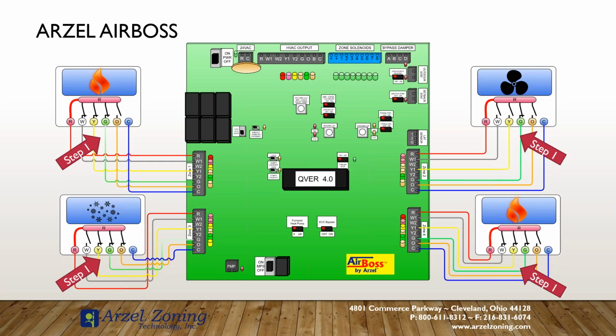Once our thermostats are on, we then go verify that the board is receiving that call. If the board is not receiving that call, then it's either a broken thermostat wire or it's a bad thermostat. So we would then have to look and see why my board is not receiving that call. And that would be voltage testing up at the thermostat itself directly. Do we have the voltage up at the thermostat where it needs to be?